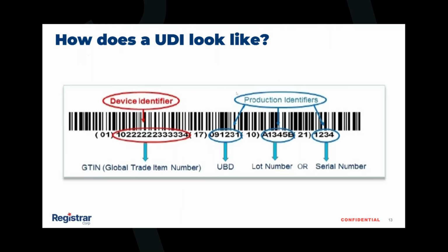How does a UDI look? This is what your barcode would look like. This is your regular barcode, the rectangular barcode. Keep in mind your barcode has two identifiers, your DI and your PI. Your DI, as you can see in red on your left, identifies the company. It will start with your company prefix number, followed by the product identifiers. The length of your UDI depends on all the information that is submitted into the GUDID. It can be shorter or it can be longer.